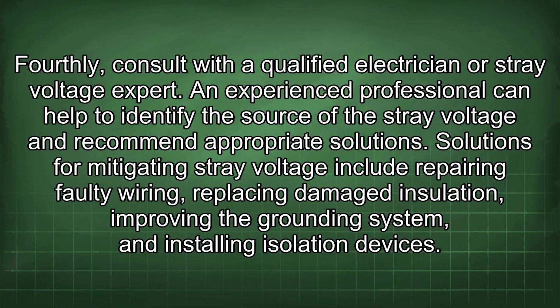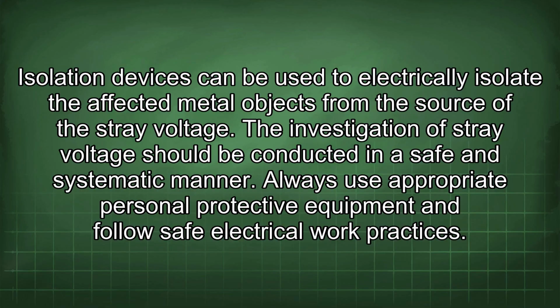An experienced professional can help to identify the source of the stray voltage and recommend appropriate solutions. Solutions for mitigating stray voltage include repairing faulty wiring, replacing damaged insulation, improving the grounding system, and installing isolation devices. Isolation devices can be used to electrically isolate the affected metal objects from the source of the stray voltage.